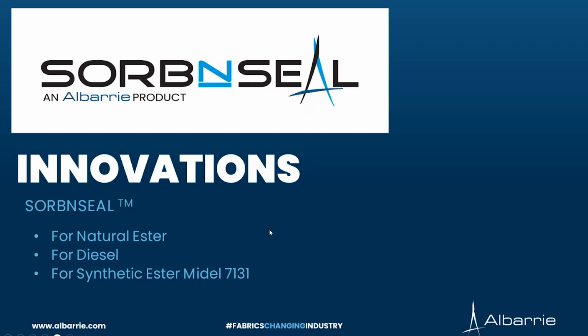As things are evolving, different types of liquids make their way to these transformers, whether it's natural ester, synthetic ester, or diesel, for example. So we did our testing through UL in the United States, and are in the process of updating some of the UL standards for above ground storage tanks. We had our very first installation in the Yukon with two 100,000 liter tanks, where we installed our containment system, because in those conditions our system is quite favorable compared to traditional concrete style containments. That pretty much concludes my presentation. If there are any residual questions, I'm happy to try and answer them.